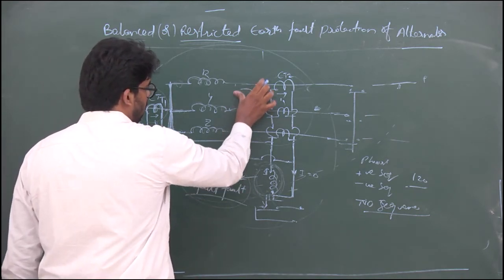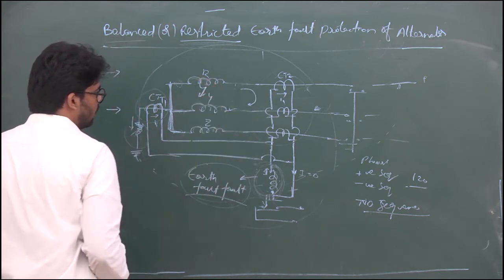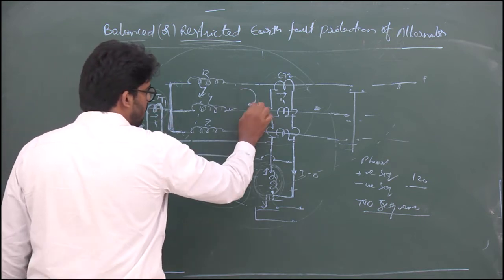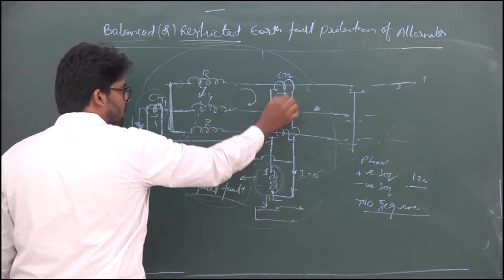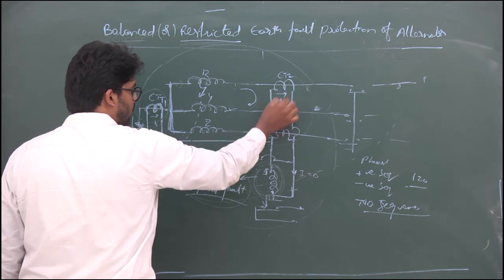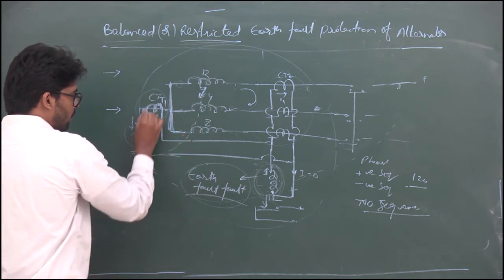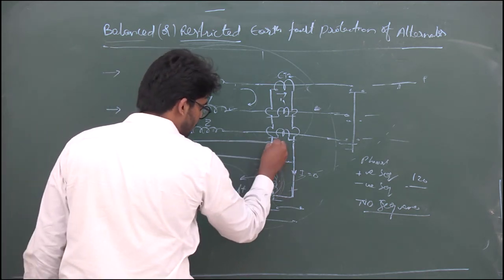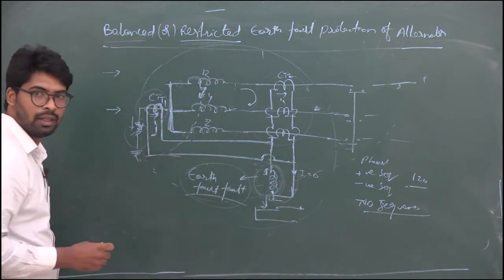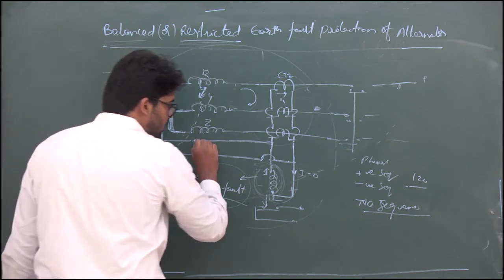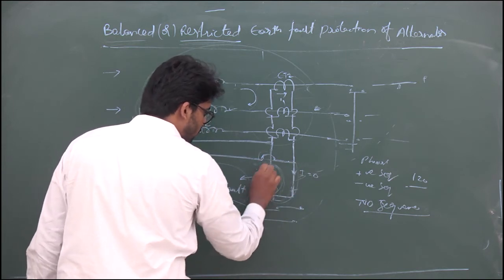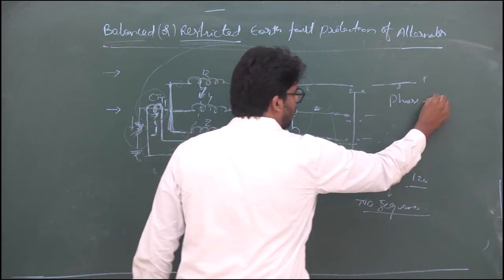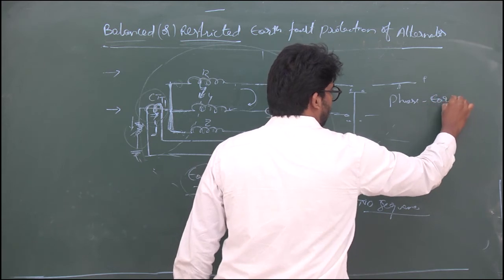But in case of a phase-to-ground fault — so this is a phase-to-ground fault — this phase-to-ground fault causes this CT to operate. When this CT operates, there is a flow of current: that is, a zero sequence current will be present, and this zero sequence current travels through the coil. That is the fault current — the zero sequence current — and if the zero sequence current is flowing through this coil, the coil will get excited and operate. So this protection is only applied for phase-to-ground fault in the fault section.